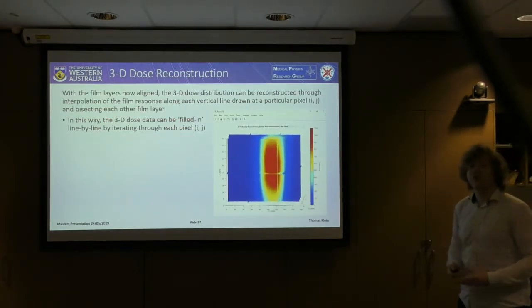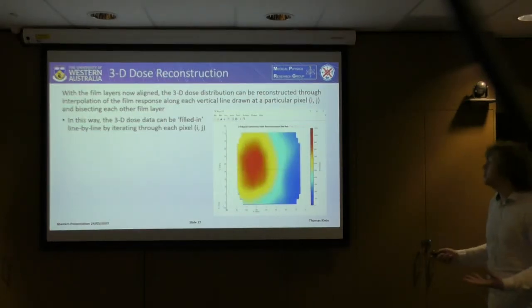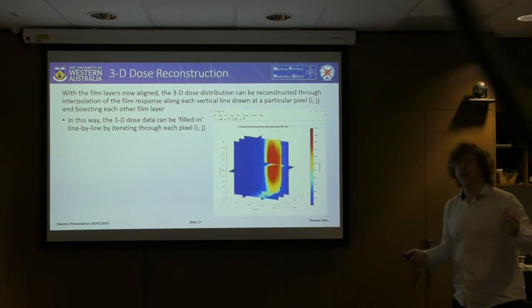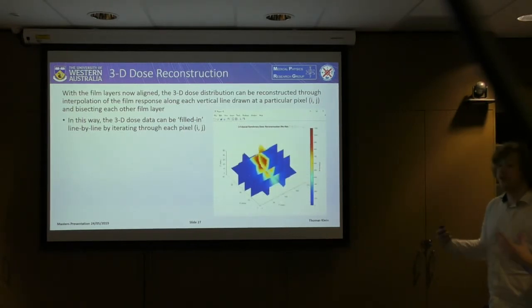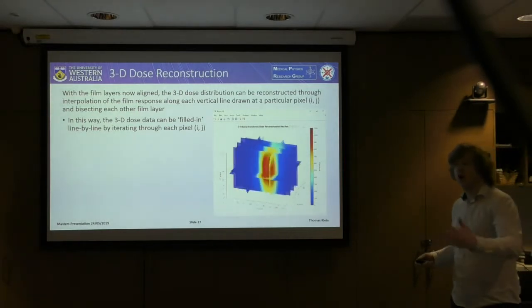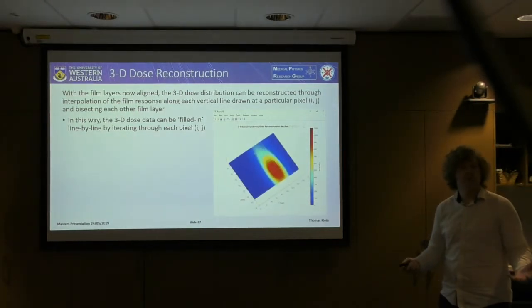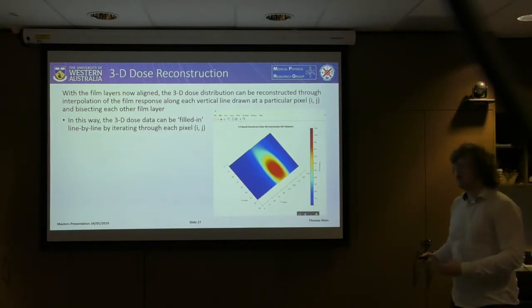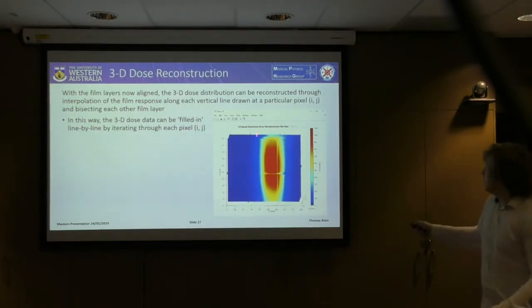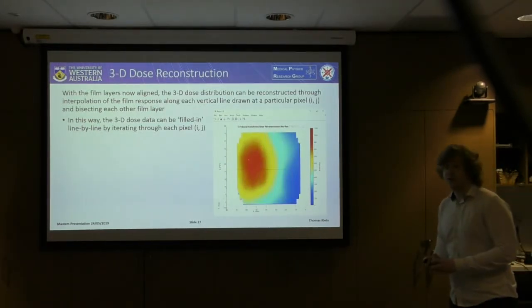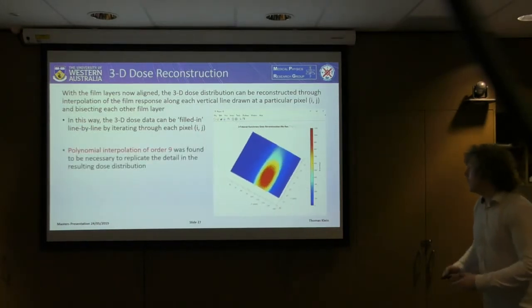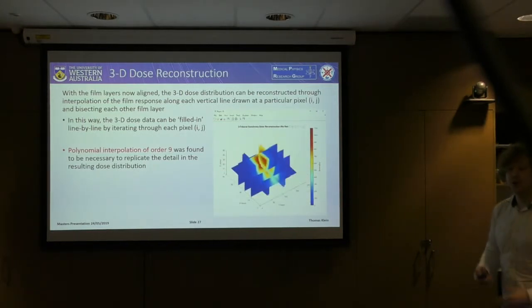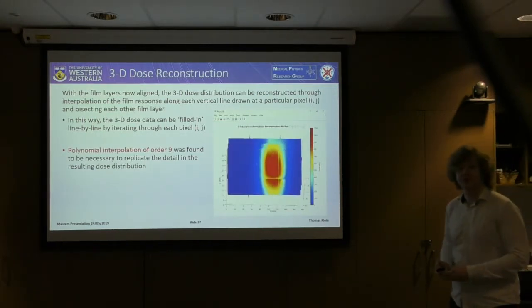With alignment complete, we reconstructed the entire 3D dose distribution. This was achieved by looking at a particular pixel in one film layer and drawing a vertical line through that same pixel in every other film layer, providing 15 data points for interpolation along that line. Repeating for every pixel fills in the entire 3D dose distribution. This dose matrix contains approximately 15 million data points. We found that polynomial interpolation of order 9 was necessary to recreate accuracy in the resulting dose distribution.